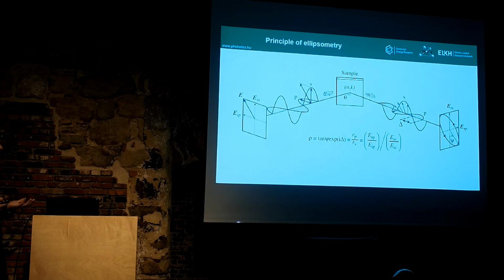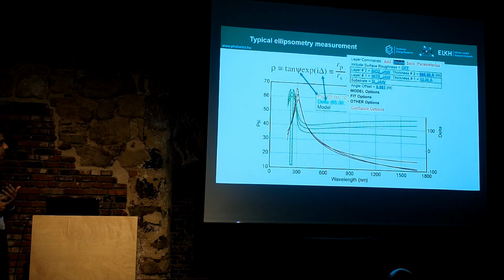If you typically use visible light like 500 nanometers, the precision can be below even 1 nanometer, and you don't have to use a coherent light source. You can use a regular lamp and a regular detector, so the instrument is very, very simple.